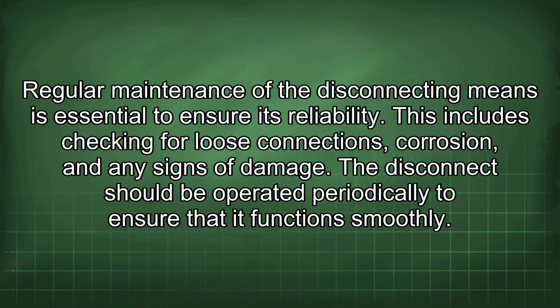Regular maintenance of the disconnecting means is essential to ensure its reliability. This includes checking for loose connections, corrosion, and any signs of damage. The disconnect should be operated periodically to ensure that it functions smoothly.